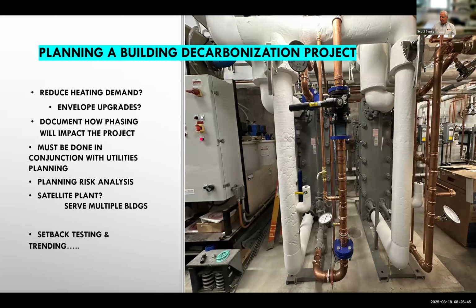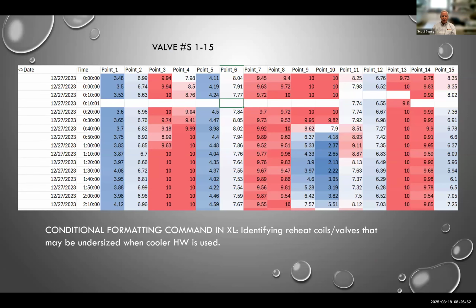Another important factor is setback testing in your design process. This is a picture of 15 control valves on reheat coils over the course of a couple of hours that we, on a stressful design type day, looked at and found the ones in red, and this is using a heat map. The valves in the red were already at like 10 volts or near 10 volts. So that means with 180 degree or 160 degree water going to the coils, they were already maxing out their operation. So we had to study these valves closer and the coils and see if we could use them or whether they needed to be replaced.